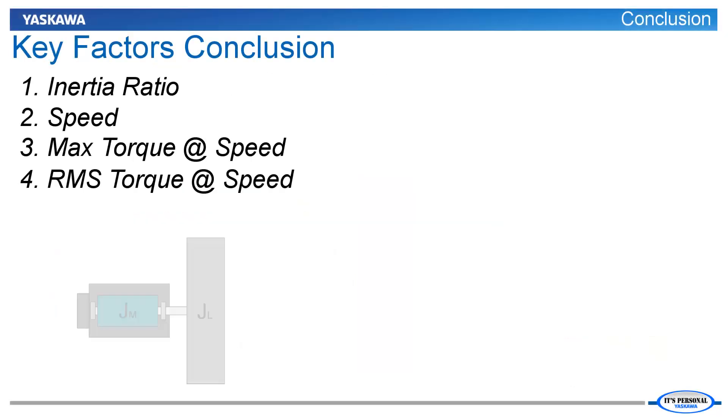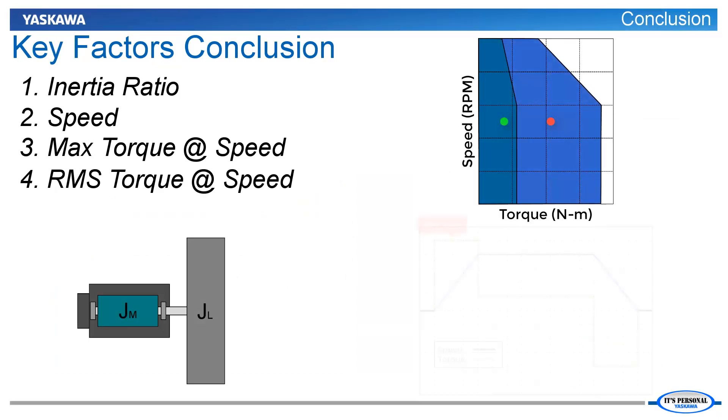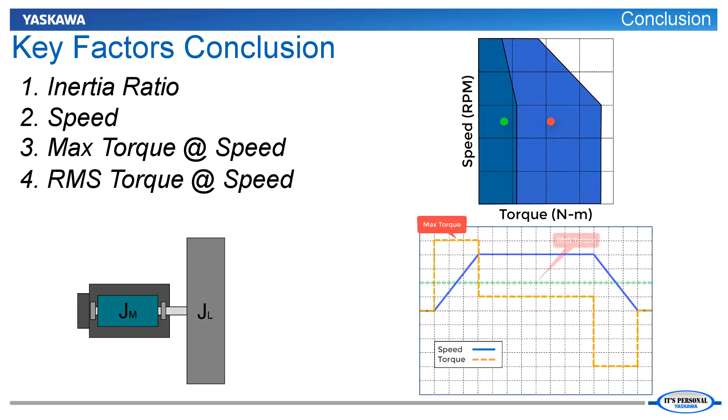Provided that the inertia ratio, speed, max torque, and RMS torque all fit the motor as described, then the motor is properly sized.